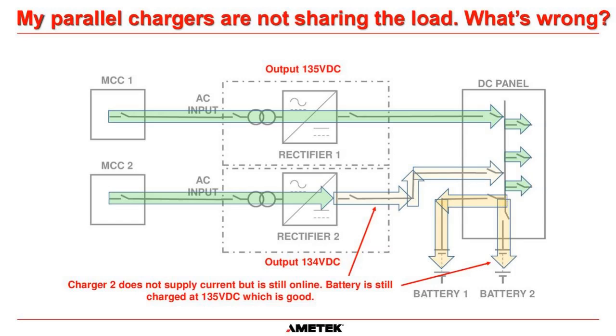So in this slide here, let's say this output here is 135 volts. This output here is 134 volts. Charger 2 will not supply current, but it is still online. And the battery is still being charged at 135 volts, which is good. So if you see 0 amps on this charger here and you're concerned that this charger has failed, there are 2 things you can do.